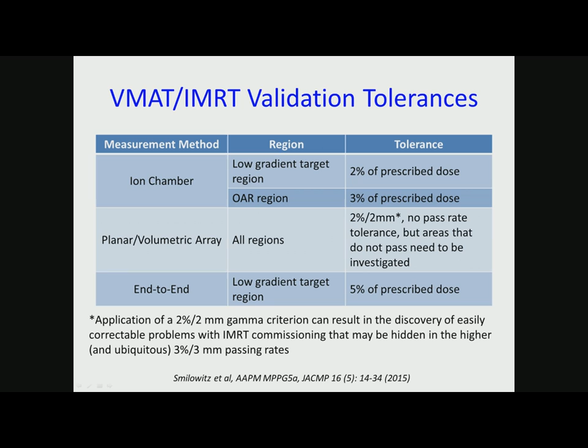The reason for that is an asterisk at the bottom of the table. It suggests that if there are some mistakes in the treatment planning system you're commissioning, it'll let you pick it up by going to a tighter tolerance. And if you're doing an end-to-end test like a phantom, you can run it through the system: CT scan it, treatment plan it, deliver it, and look at the results. It's a 5% tolerance. So I went back to our resident and I said, hey, this is kind of interesting. Let's go and look at some of our cases.